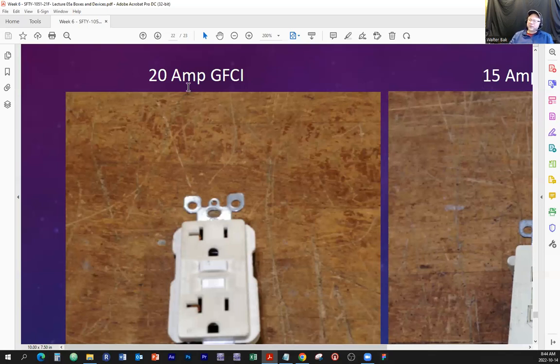And if the electrical panel is able to supply less, it will still try to draw. If the cables are designed or rated for less than 20 amps, it will still pull 20 amps through the thinner cables, which might cause them to overheat, but the load doesn't care. Actually, there's not even a question about caring, because the load just is. It's not aware of itself. The load just takes the amps of whatever it's rated for.